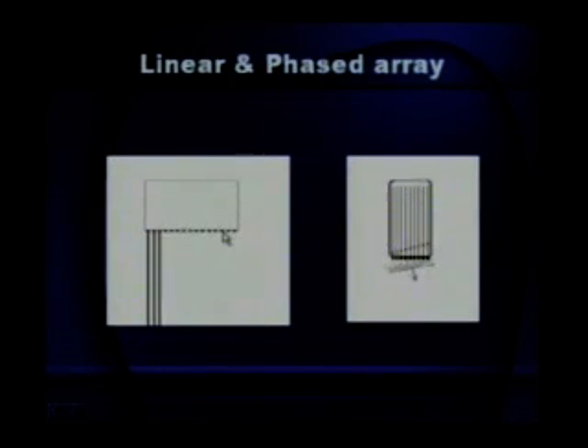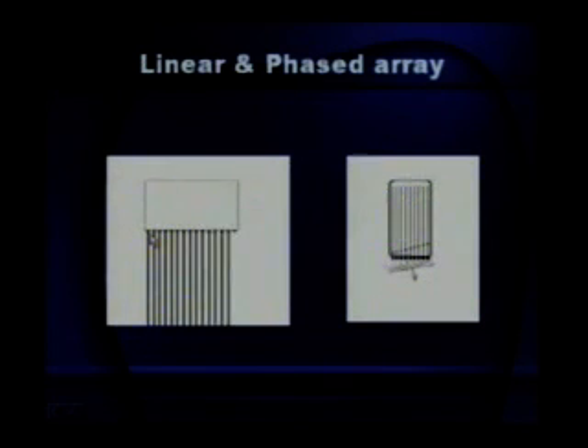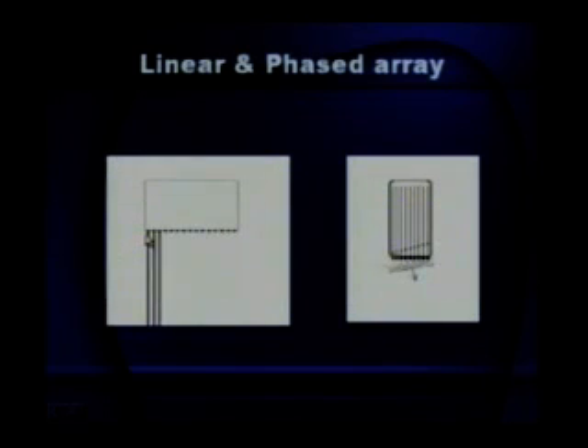This is an example of a linear array probe. In linear array, there are multiple crystals which are arranged in a series, and each crystal fires sequentially. So when one crystal fires, it results in formation of a beam. After some time, the second crystal fires, and that forms another beam. That is how the ultrasound beam is moved from one end of the image to the other end, and we get a parallel broad beam.